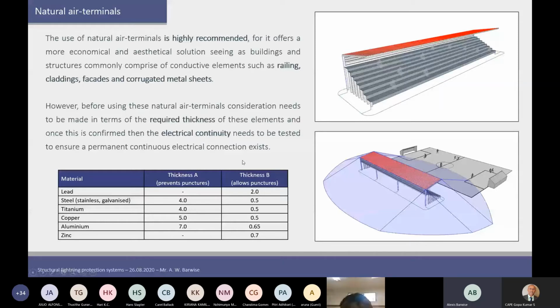Let's take, for instance, as I gave the example, galvanized steel. In thickness A, column A, we have 4 millimeters, which is really thick. And in thickness B, we have 0.5 millimeters, a standard type of sheet. The difference between A and B is whether you are worried about lightning puncturing. Remember I stated earlier, lightning has 3 characteristics, and one of those was the specific energy, the heat exerted by the lightning current itself when it's intercepted. So if you want to handle that heat, not cause a hot spot or a puncturing of the roof or of a system, you have to have a very thick material, 4 millimeters at least.